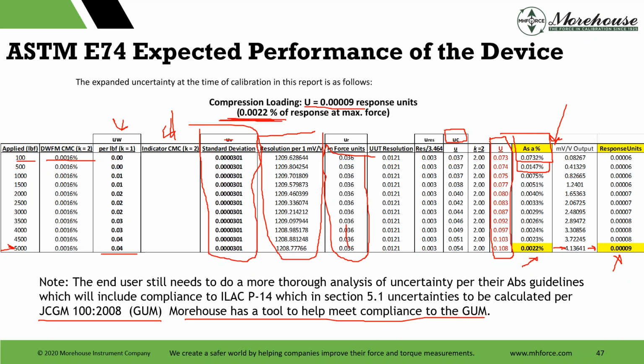This is where we get into the secondary standards. You say, hey, can one load cell do it all? If you're using secondary standards and want to maintain better than 0.02, more than likely, the maximum you're going to be able to get is from 10 to 20% of the loading range. And therefore, someone buys a PCM or other machine, we usually recommend 2 to 3 load cells because you're going to have to switch up depending on what you want to maintain. If you want to maintain better than 0.01 for some ISO requirements, you're going to have to do a whole heck of a lot more.